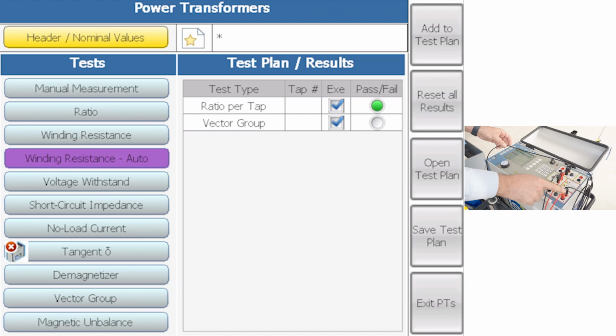And in the same points, neutral and phase A, because now I will measure the winding resistance of phase A, I'm also measuring the voltage drop. Because as we know, in order to measure resistance, I need to generate current and measure the voltage. So accurate measurement of the current, which I'm generating, measurement of the voltage drop, and the system STS automatically calculates the winding resistance.